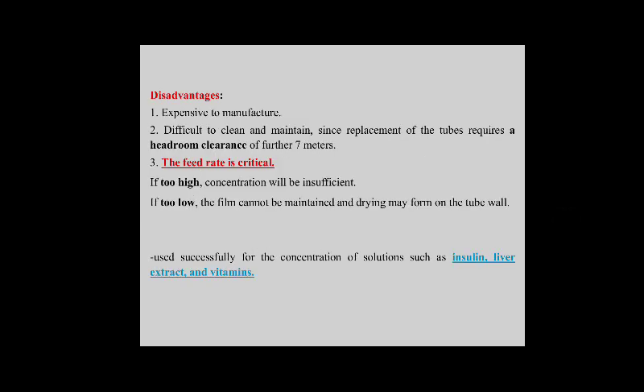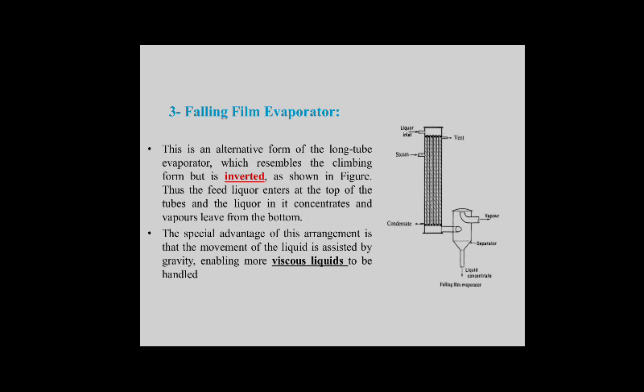Disadvantages of the climbing film evaporator: expensive to manufacture; difficult to clean and maintain; tubes require headroom clearance of about seven meters; the feed rate is critical — if too high, concentration will be insufficient; if too low, the film cannot be maintained and drying may form on the tube wall. It is used successfully for concentration of solutions such as insulin, liver extracts, and vitamins.